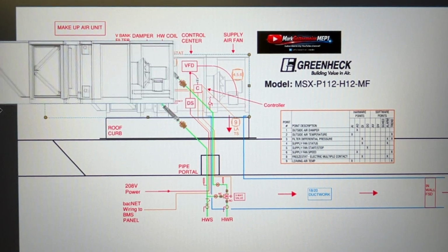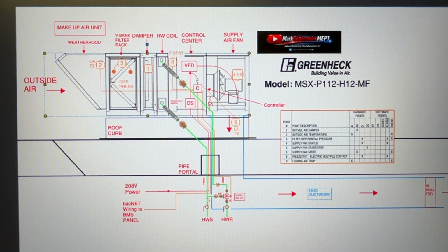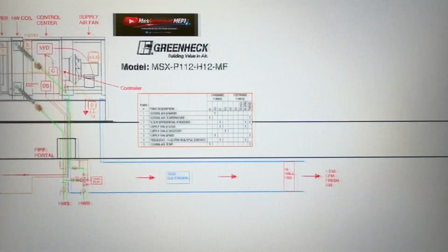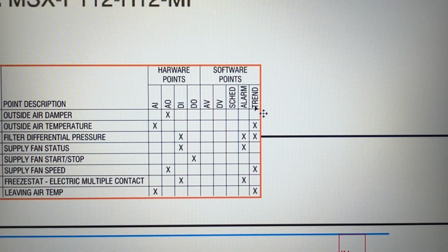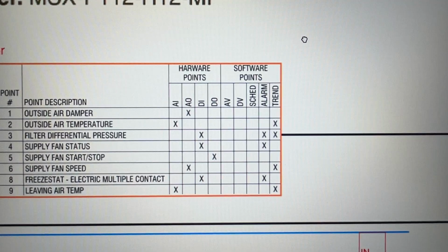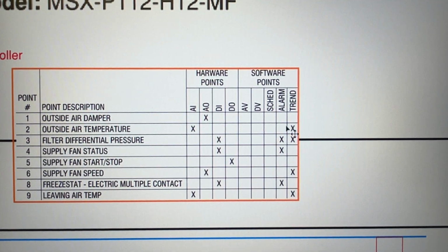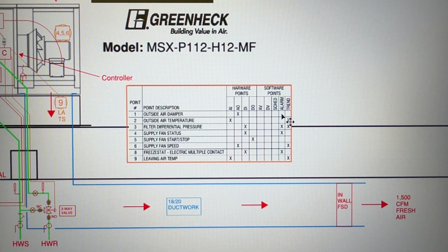So just to wrap up the controls side of this, I'll show you down here. We've got alarms, and we've got the trending. These six X's here on the trend will be saved in the building management system. They will keep a constant log of what those are doing, so that if anything happens, you can always go back and see what it was doing and when, what time of year. So it gives some ability to fact check what's going on if there were issues. Then they also have an alarm here. These three points with X's will be alarms if they end up failing. So on the BMS side, those were just two important things that you should know about as well.